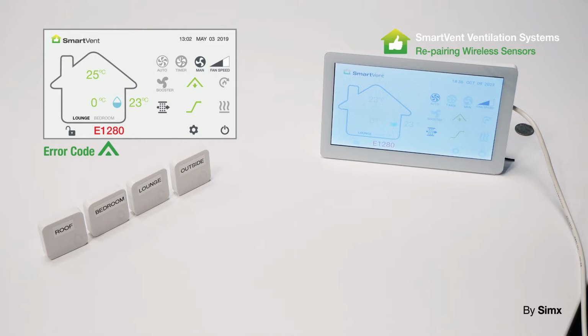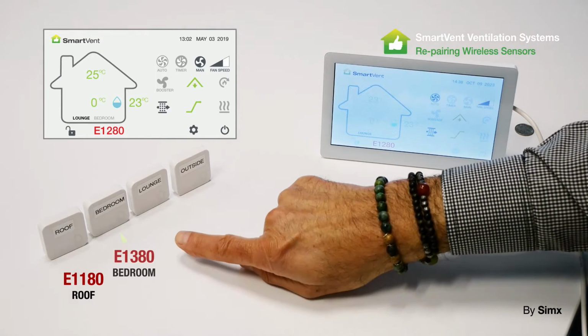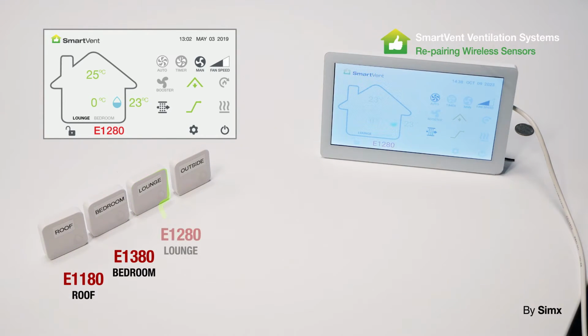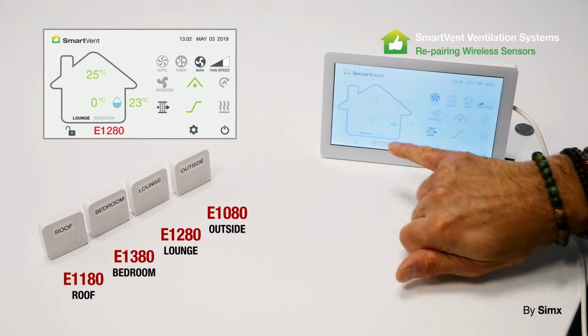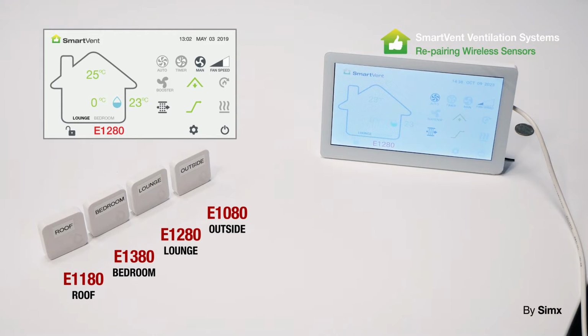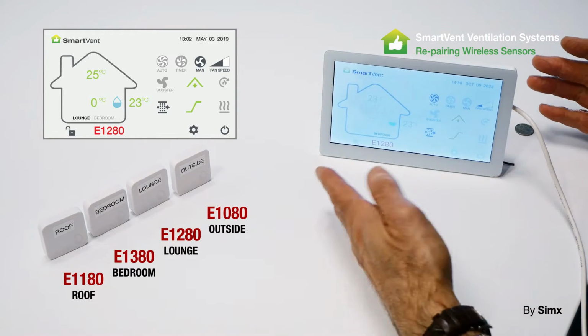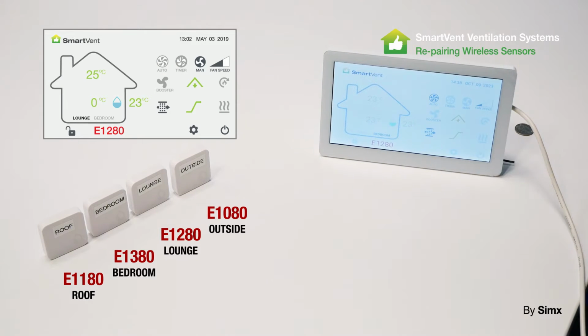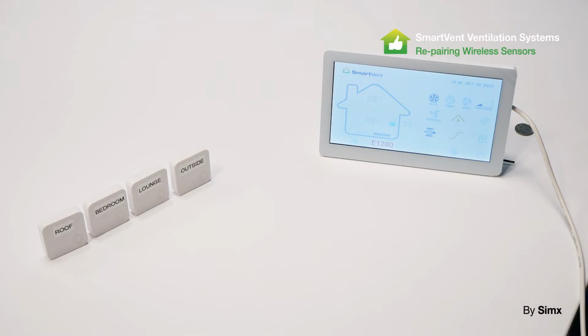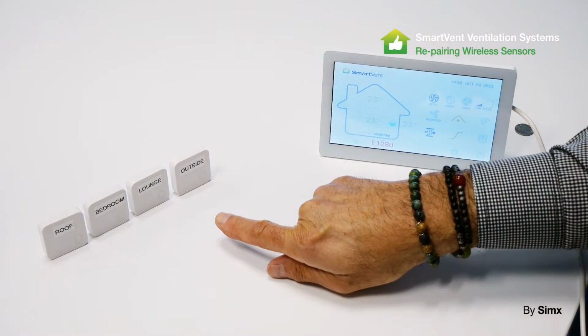So basically the way these error codes read: E1180 is the roof sensor, E1380 is the bedroom sensor, E1280 is the lounge, and E1080 is the outside. You can see here that the lounge isn't reading anything at the moment, it's reading 0. The bedroom is still reading 23 degrees, and the outside's still reading 23 degrees. So it's pointing to the fact that the lounge sensor is faulty.